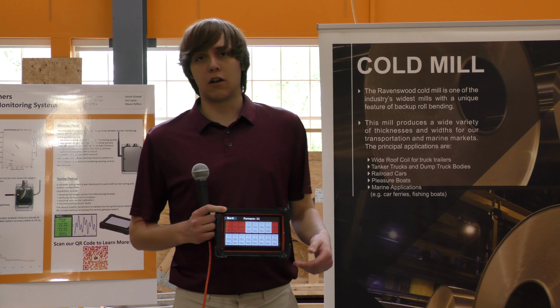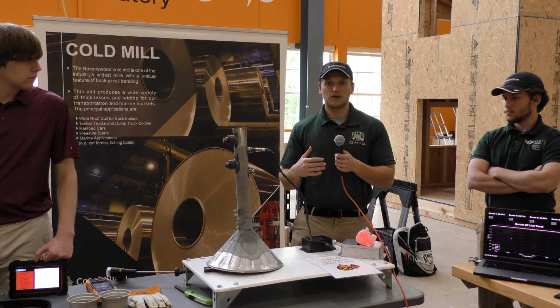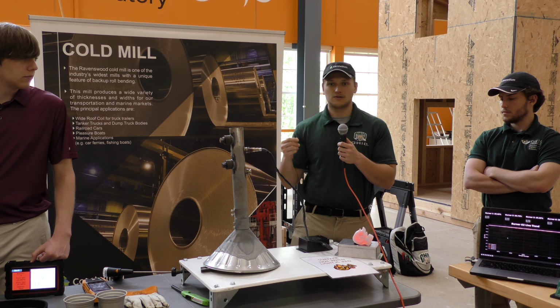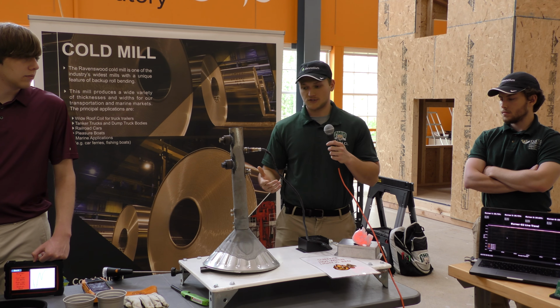Like he was saying, this is kind of like our demo. This is acting as the flue pipe that our oxygen sensor will actually go into at the plant. And then it'll come to the monitoring panel that Garrett was talking about. And then this will send the signal out to the Ethernet panel that it'll split into the plant network that's shown on the laptop and then to the tuning device that operators there will be able to hand hold and go adjust the oxygen on the bottom of the furnaces.